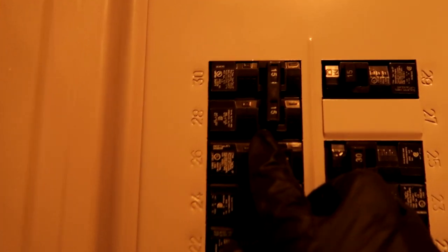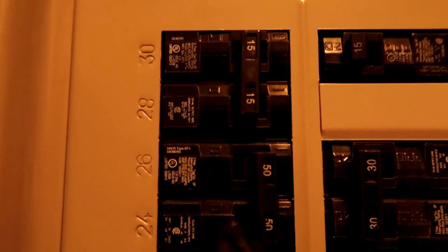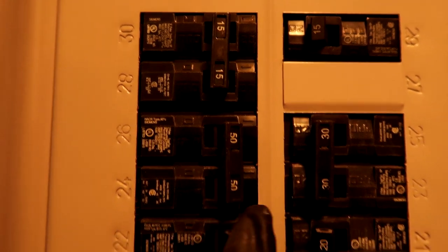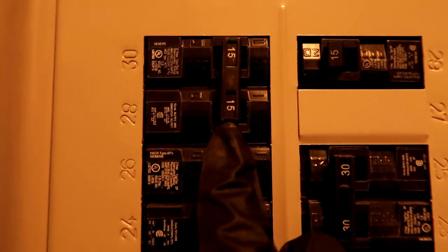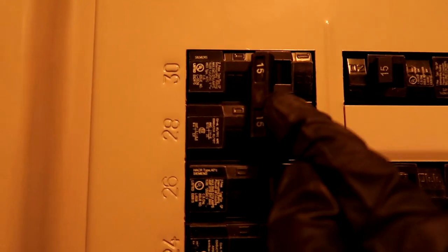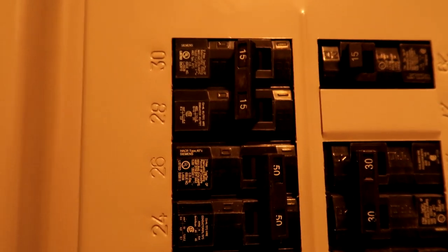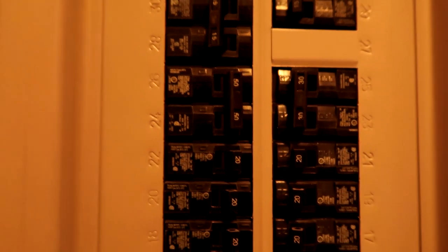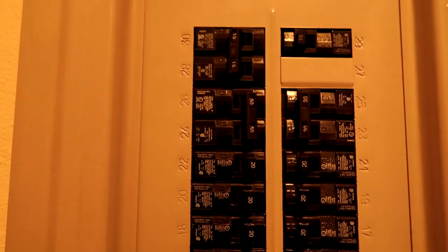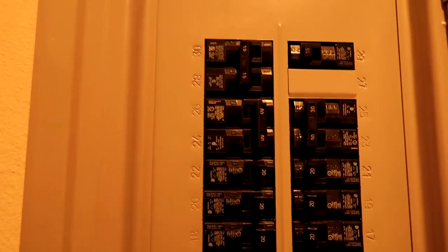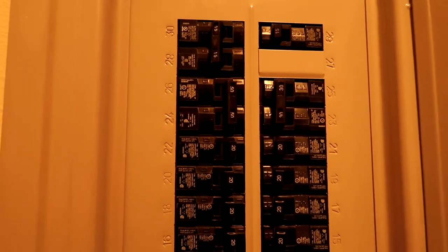Yep, breaker is tripped. See how those are a little further over and this one's in the middle? Yeah, bet we got us a bad hard start. Seeing it a bunch of times out here. When that hard start starts going bad, trips the breaker. Let's go test it.